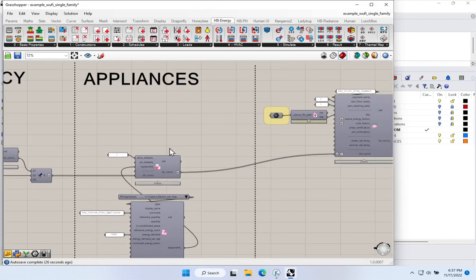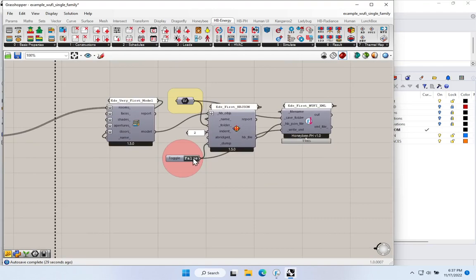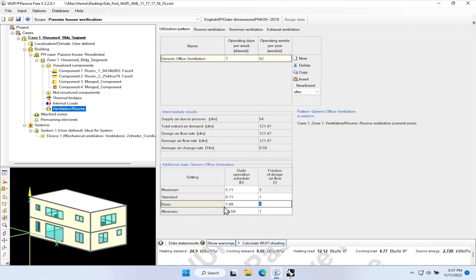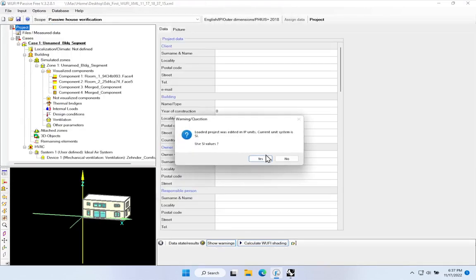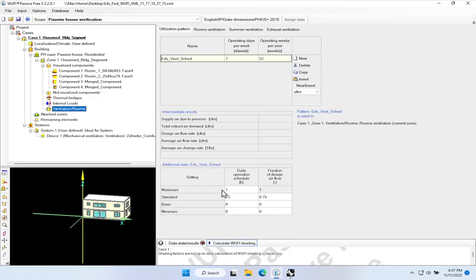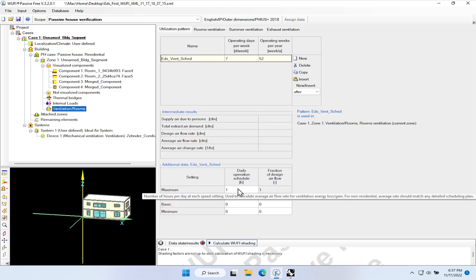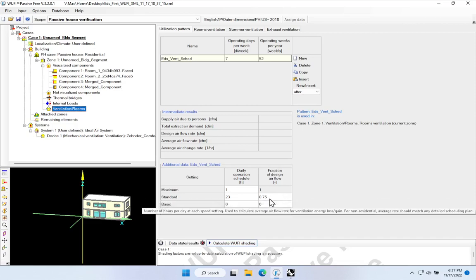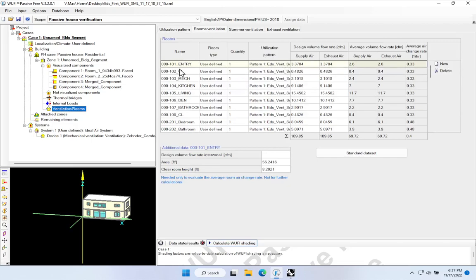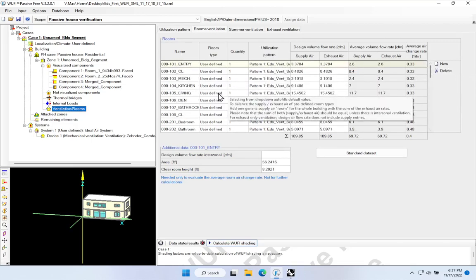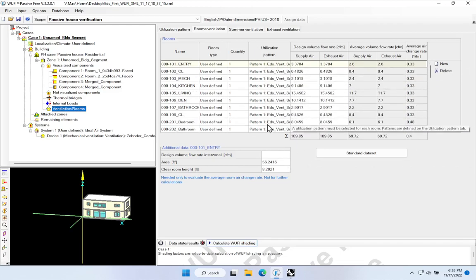Let's take a look at what that looks like. I'll go ahead and write out my WUFI Passive file, then shift back to WUFI Passive. Notice what our schedule looks like now — I'll go to File, Open, navigate to my desktop, choose the newest timestamp. Now if we go to our Ventilation Rooms, notice that I now have my maximum running one hour a day at 100% fan speed, and my standard running 23 hours a day at 75% fan speed. Ed's Vent Schedule is now being applied as the schedule for all spaces. Notice the loads haven't changed — we've only changed the schedule of operation.